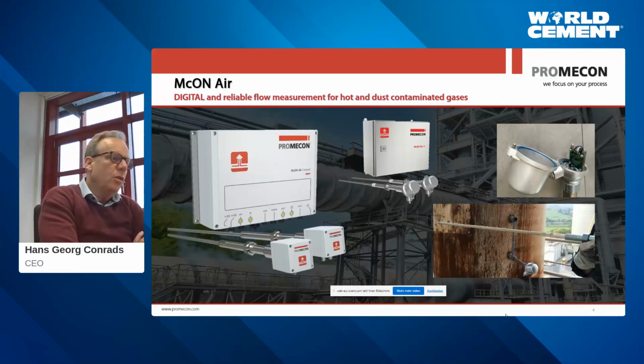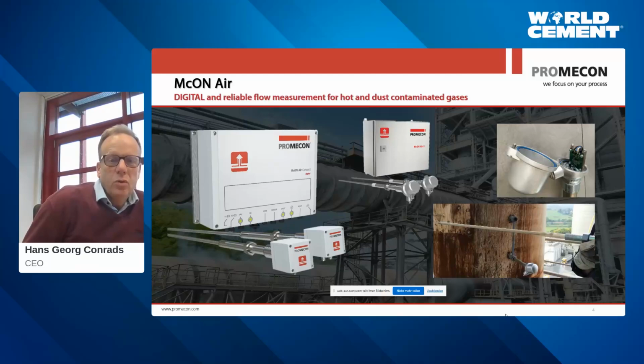technology for. To give you an example, please take a look at the picture at the lower right-hand side, where someone has taken one of our sensors out of the gas duct. You can see that the sensor is completely covered with clinker dust or with raw meal dust. And as you can see, this sensor needs no cleaning in order to measure properly. Sensors that are covered like this can measure perfectly with perfect accuracy. There's no need to clean or to recalibrate them. And that's the main feature and the main value of our measurement. It is that you put it in, it's digital, and it doesn't drift, and therefore you always get an accurate result over the long term, and there's no regular need for maintenance for this measurement. And why this is so, I would like to explain in the following slides.